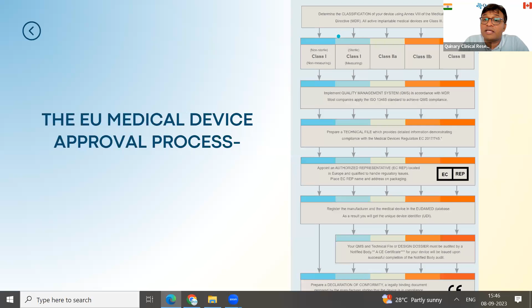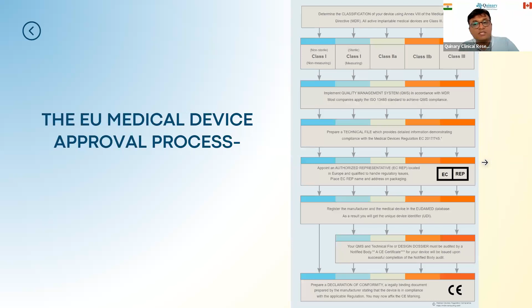These are the different classifications country-wise. Again, they have a submission of the quality management system and a submission of the plan, and at the end, your QMS and technical file for the design dossier must be audited by the notified body, and a CE certificate for your device will be issued. So after scrutiny, they will issue the CE certificate. These are the requirements. This is just a touch base that if you are planning to market your device in Europe and the US, there is a separate set of regulations which you have to follow and comply with.